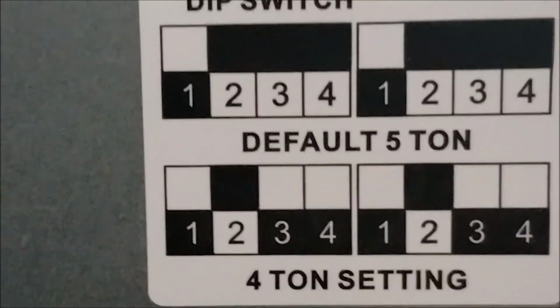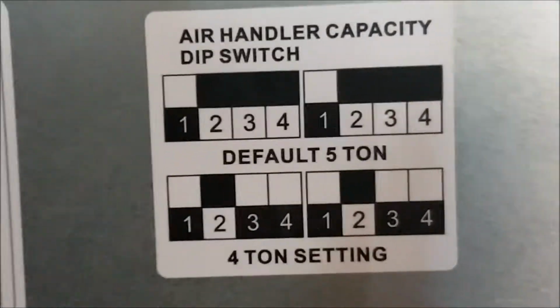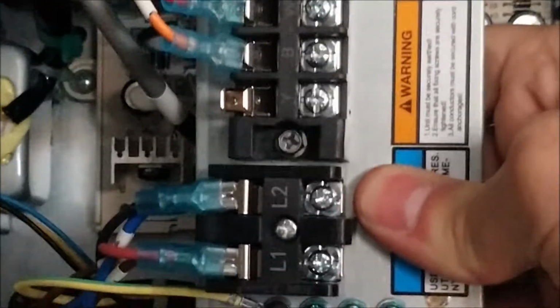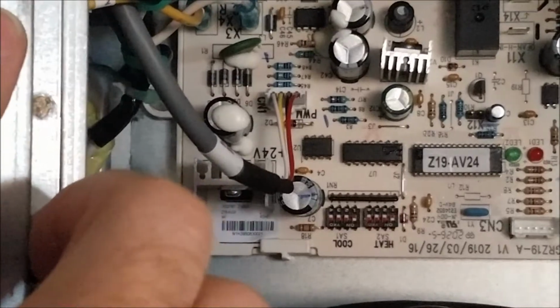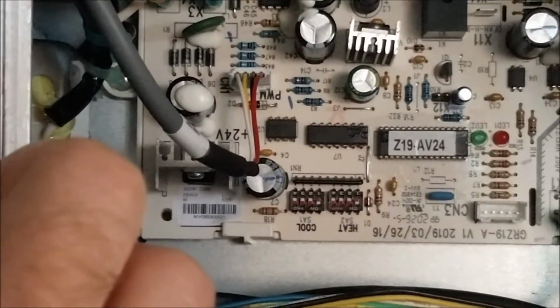But so I'm going to go into the 4 ton setting, and that'll be used for my system. But again, you can do this all from the air handler. And I'm pretty sure it sets the blower speed here, and so basically there's the input for your AC and your thermostat wire. It's hiding behind here, so you just gotta kind of pull that out and then unscrew it, and there's access to your configuration switches.